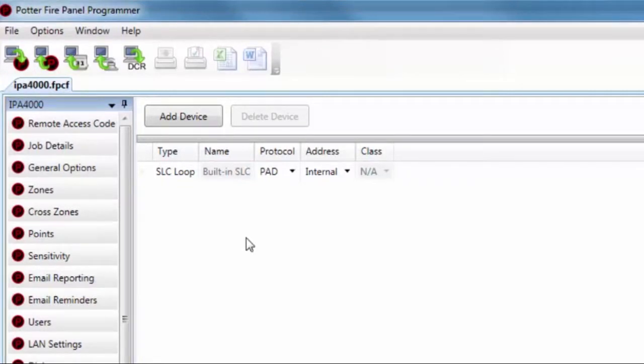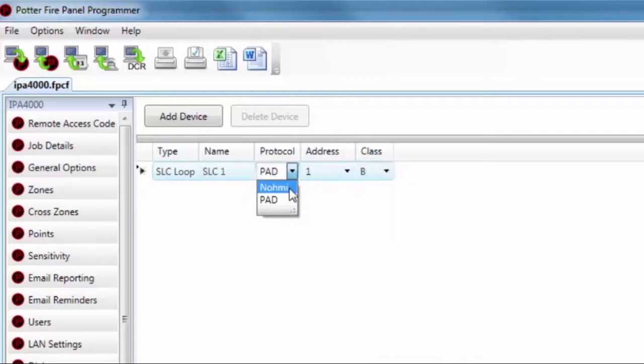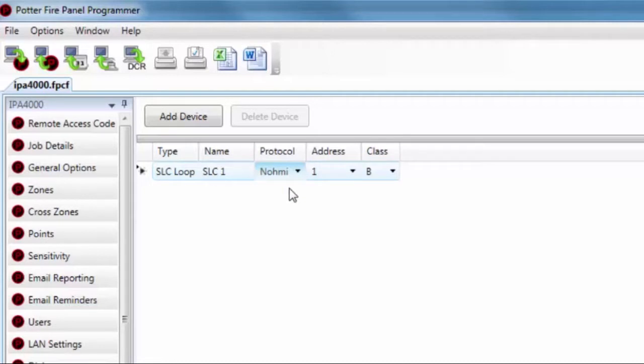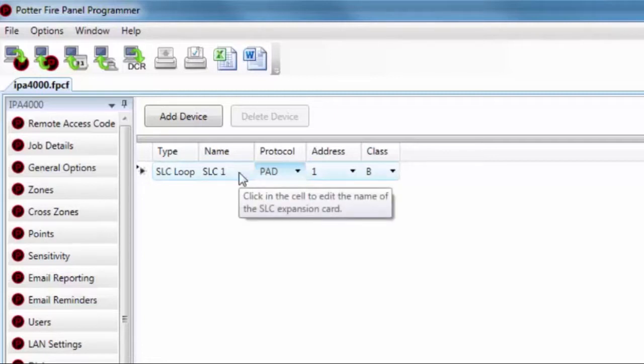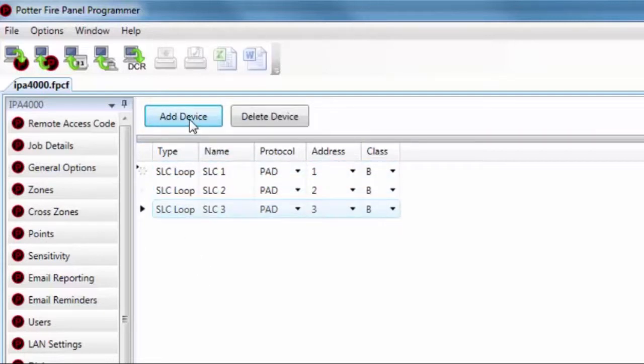The internal SLC loop must be PAD protocol. If you want to install NOMI protocol devices on the IPA-60 or IPA-100, change the address of the internal SLC loop to 1 and change the protocol to NOMI. This disables the internal SLC loop and allows you to install an SLC 127, which connects NOMI protocol devices to the system. You can also keep PAD protocol and install a PAD 100 SLCE for remote mounting of the SLC loop. Through the Name column, you can customize the SLC name. In this section, we are simply adding the P-Link device itself.